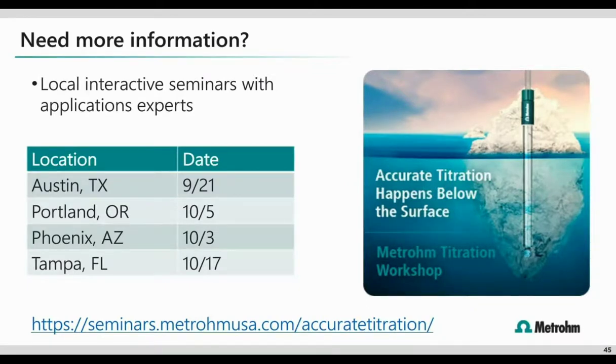Excellent, thank you. Now, our next question has to do with storage recommendations, and why do long-term storage recommendations differ from short-term storage for metal probes? So on this one, we're talking specifically about metal probes. If you've got an electrode that is basically two metal sheets, so think no reference electrolyte solution, this is something that we can store dry. Those metal surfaces don't need any contact with moisture or reference electrode. This is something you would use maybe in a vitamin C application. So think redox, two platinum sheet tip electrodes.